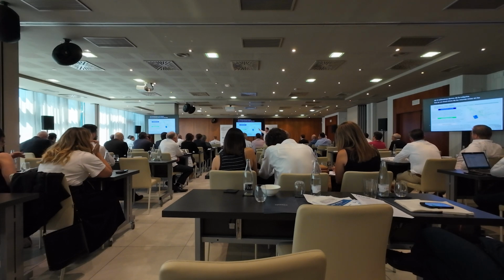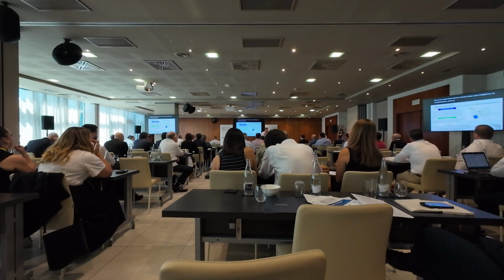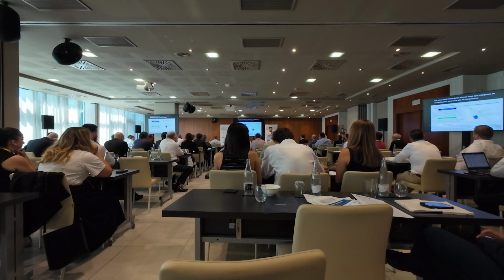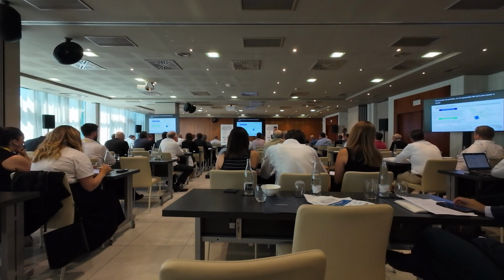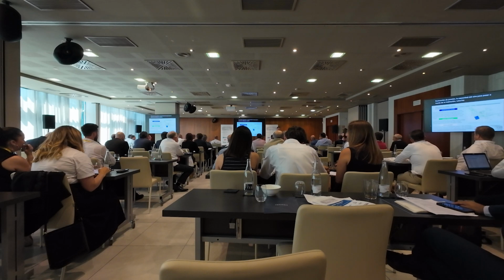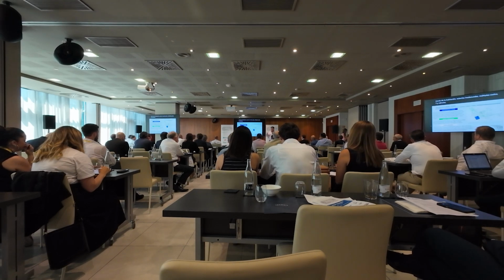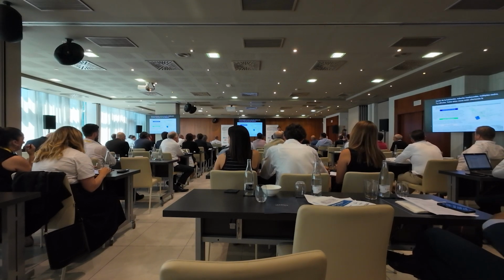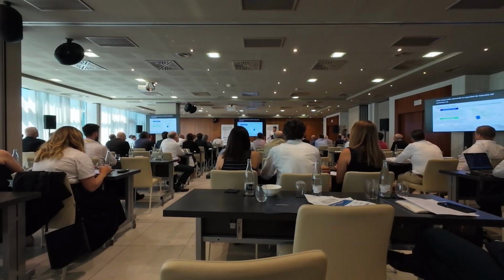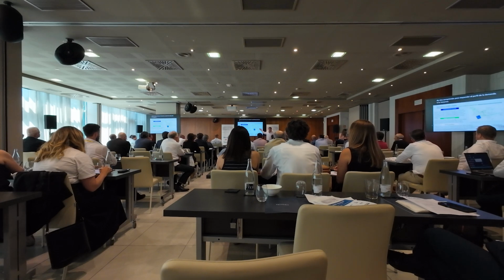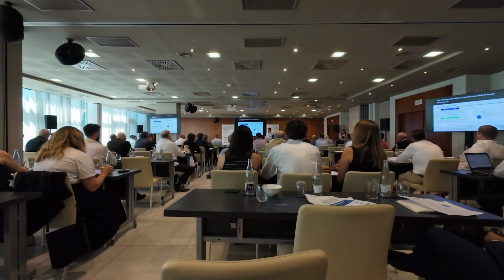But in the compressor room, we think about pressure fluctuation, the ability of the air to get through the room, inadequate piping, multiple elbows and T's and valves. All of these things are affecting the ability of the compressed air supply to respond to the demand profile. And we make it harder than it has to be if we don't take it into account.